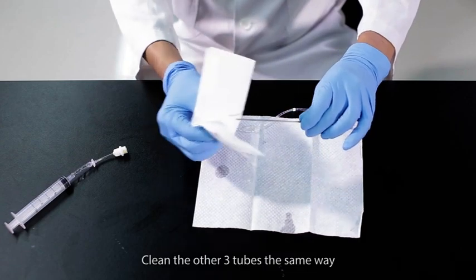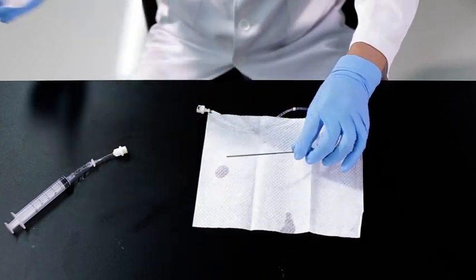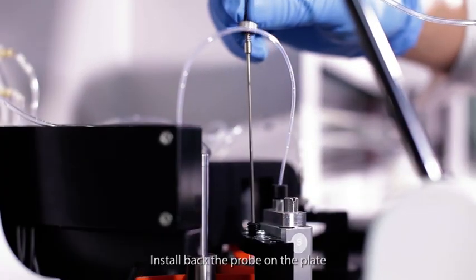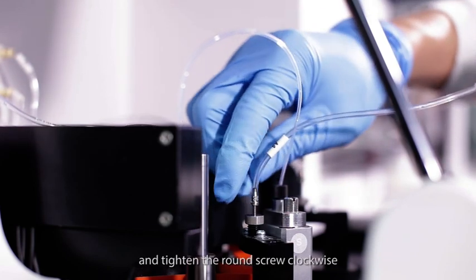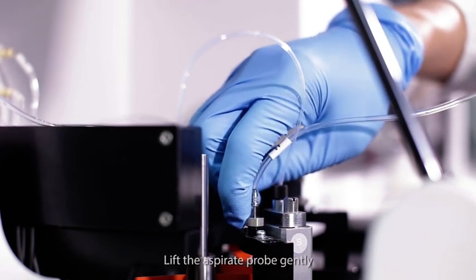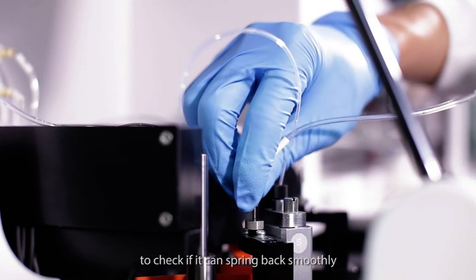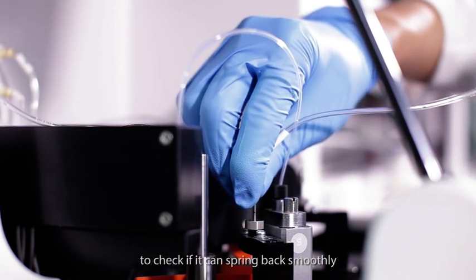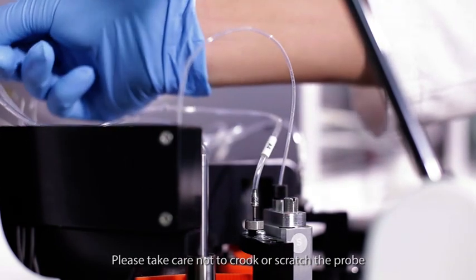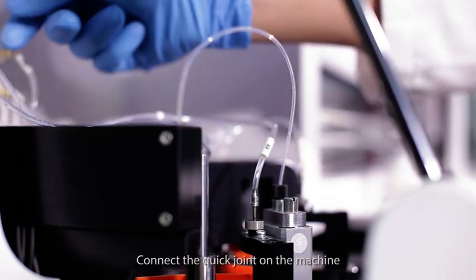Clean the other three tubes the same way. Install back the probe on the plate and tighten the round screw clockwise. Lift the aspirate probe gently and check if it can spring back smoothly. Please take care not to crook or scratch the probe. Connect the quick joint on the machine.